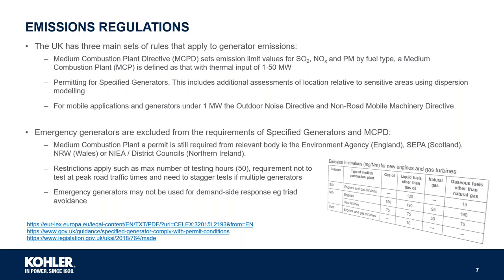So what are the emissions regulations? In the UK and Europe there are three main sets of rules that apply to generator emissions. The Medium Combustion Plant Directive sets emissions limits for sulfur oxide, NOx, and particulate matter by fuel type. A medium combustion plant is defined as one with a thermal input of between 1 and 50 megawatts. Permitting for specified generators includes an additional assessment of location relative to sensitive areas, using dispersion modelling for example.